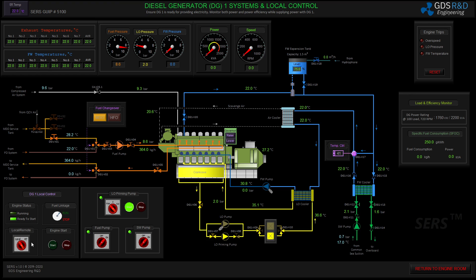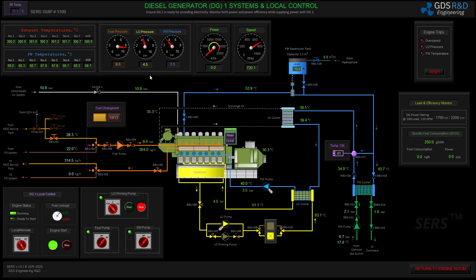I will start the generator in local mode. The oil pressure and fresh water pressure are rising. The engine speed is supposed to reach up to 720 RPM. All parameters look stable.